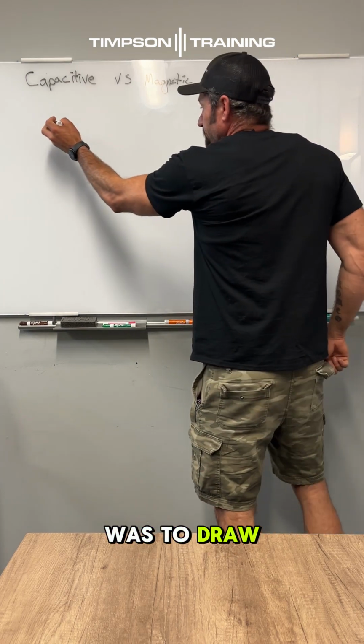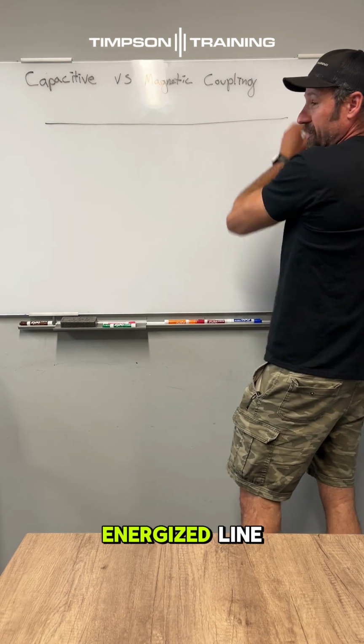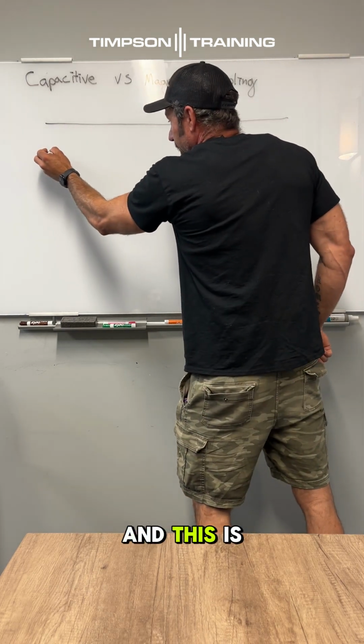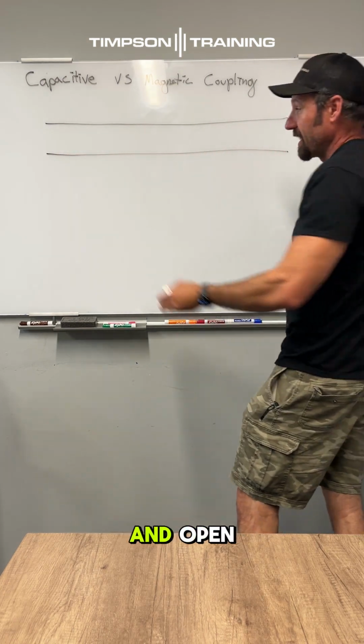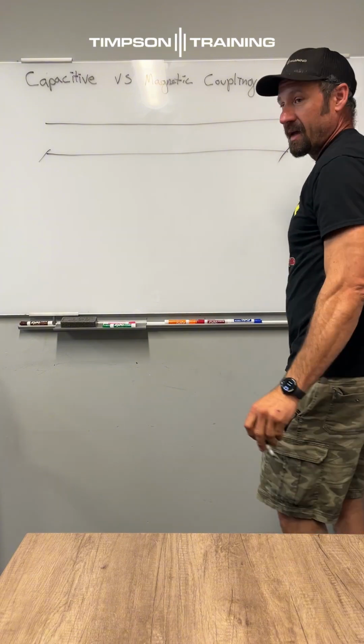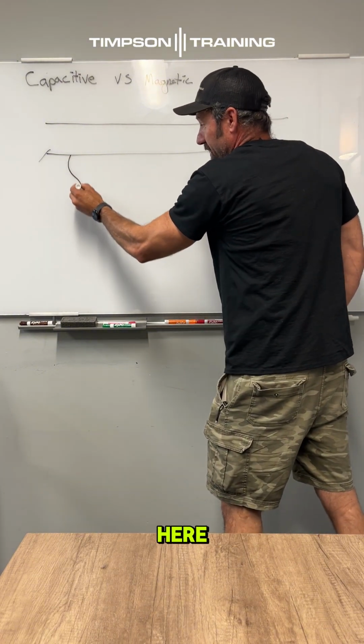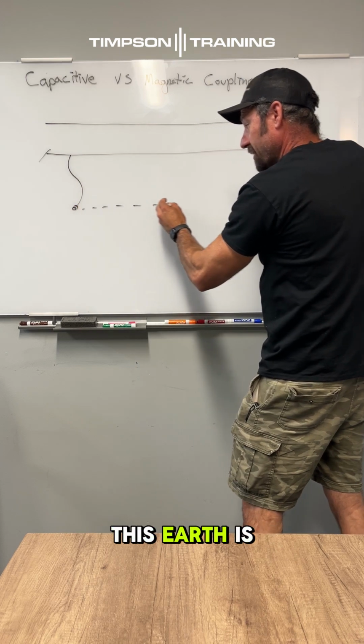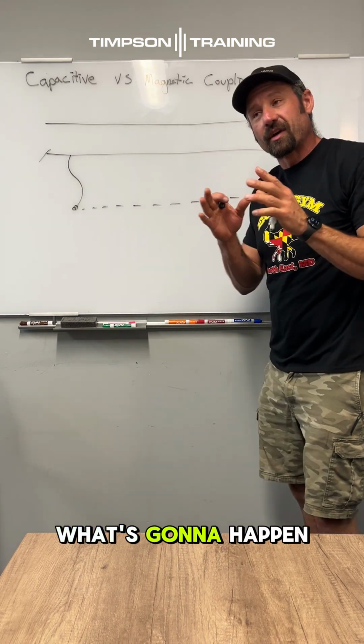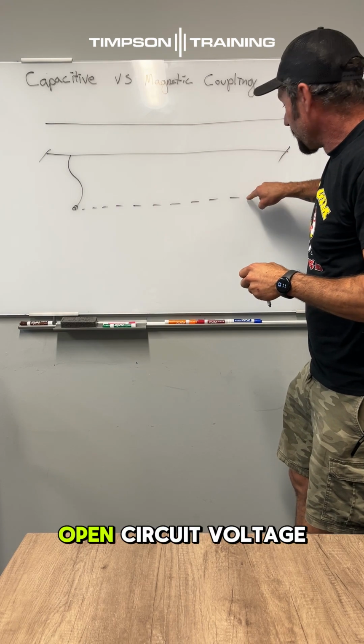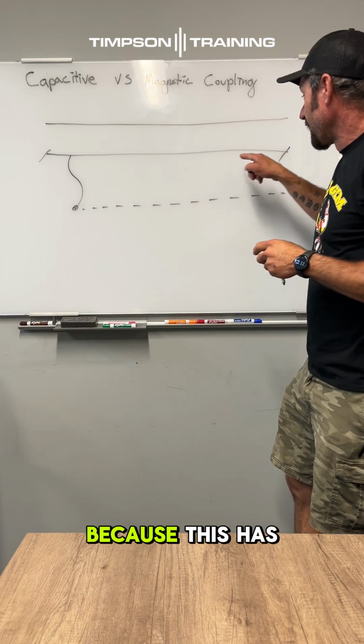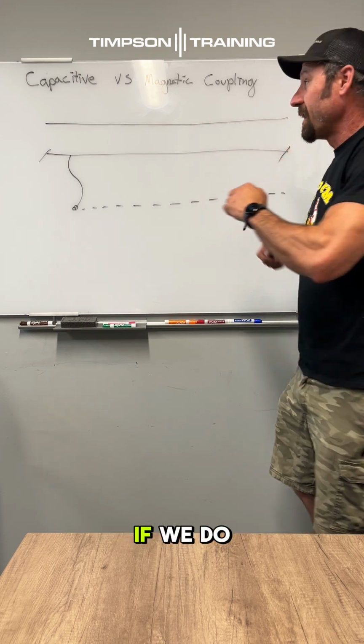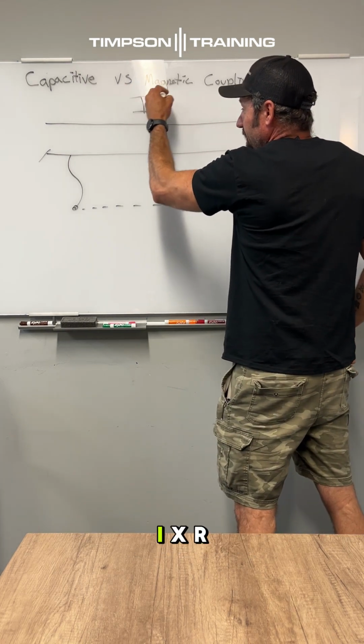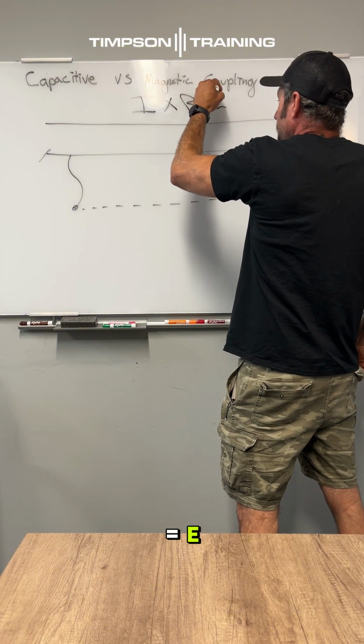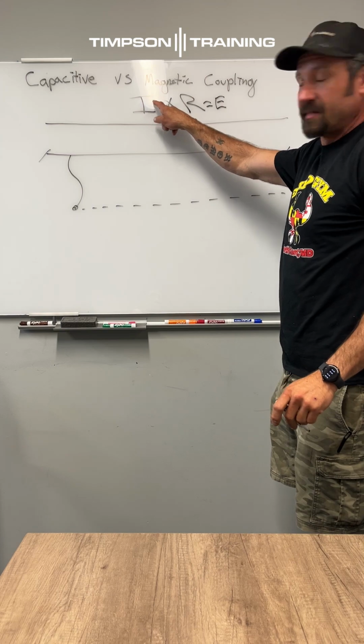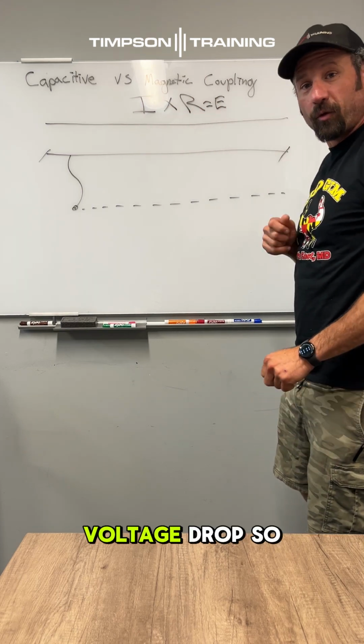So if I was to draw a line and say this is my energized line, and this is my adjacent line that is dead and open. If I install a ground right here, and we imagine this earth is another conductor, what's going to happen is you have an open circuit voltage here. Because this has a heavy current induced on it, if we do this normal calculation, I times R equals E, we have a current and we put a resistance in it, we get a voltage drop.